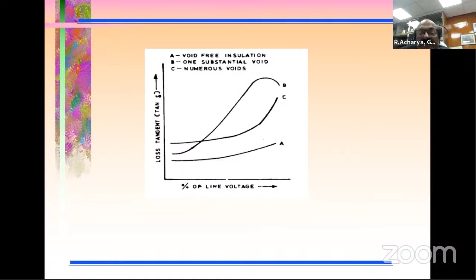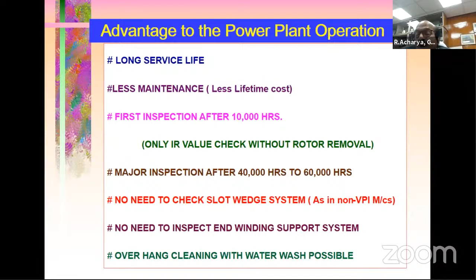It doesn't require maintenance even for 5 years. If properly taken care of, 5 years, no maintenance. You just open it, check the cleanliness, and put it back. There's no need to check tightness or wedges, nothing of that nature. It's a complete monolith. That's the advantage of a total VPI insulation system, and that's why the overall lifetime cost to power plant operators is very negligible as far as the generator is concerned. But what are the hazards and risks?